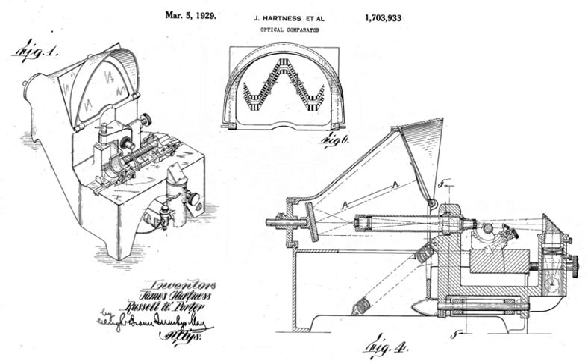Another way is that various points on the silhouette are lined up with the reticle at the center point of the screen, one after another, by moving the stage on which the part sits, and a digital readout reports how far the stage moved to reach those points.